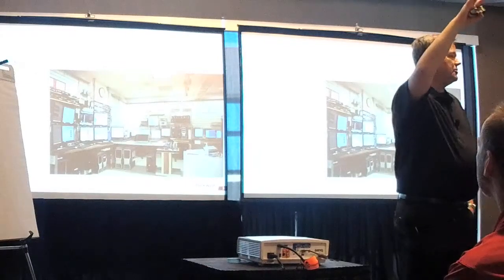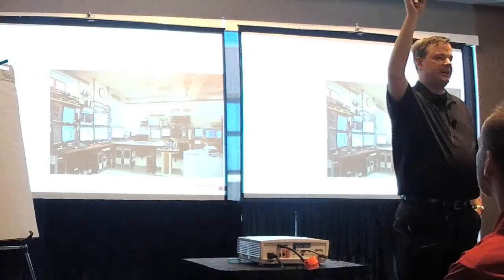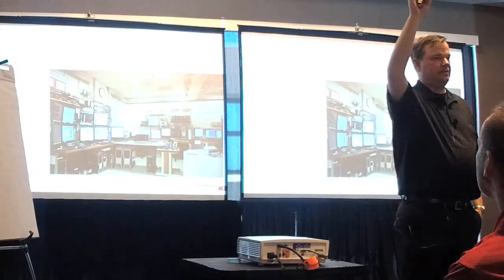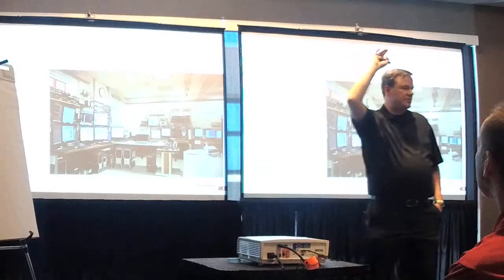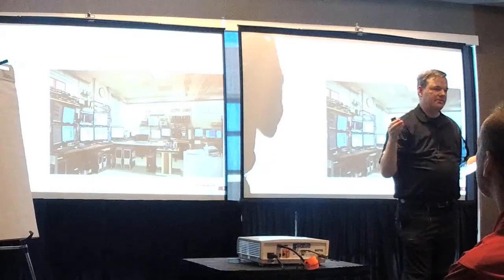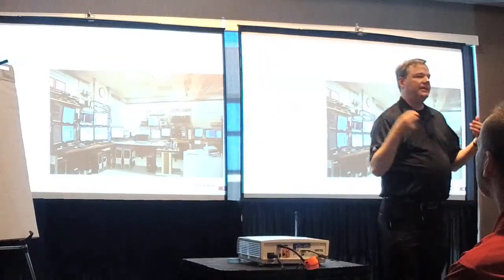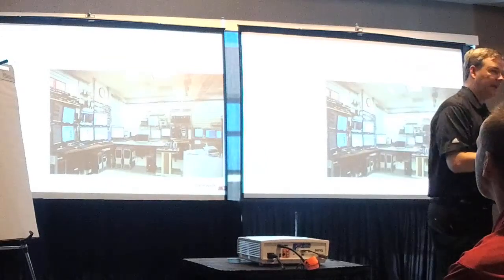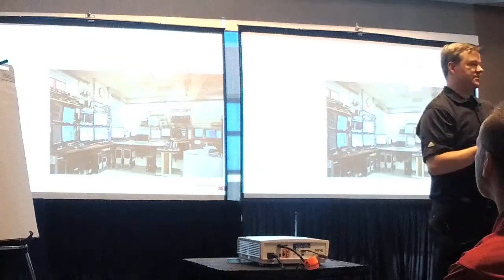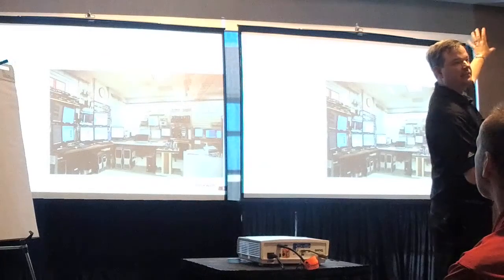When we say break it, we talk about things like critical system attributes. When I put a button on the screen and 15 seconds later something happens, no good. So we stress the system and see when that display call-up time is broken, say over 2 seconds, over a second. If we don't paint trends in the appropriate space, if we don't serve alarms capably, we stress the system and load those controllers until we see those breaking points happen. And it's a living lab.